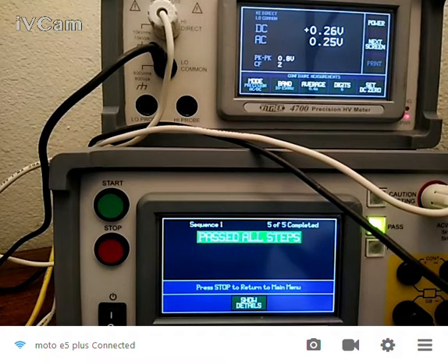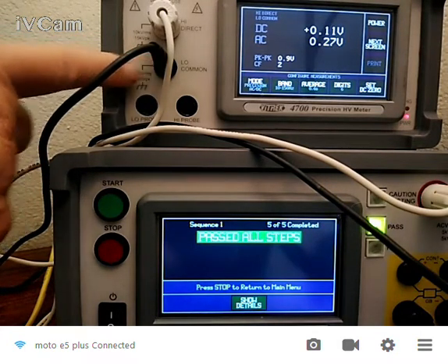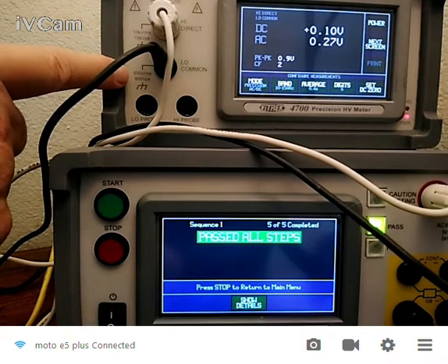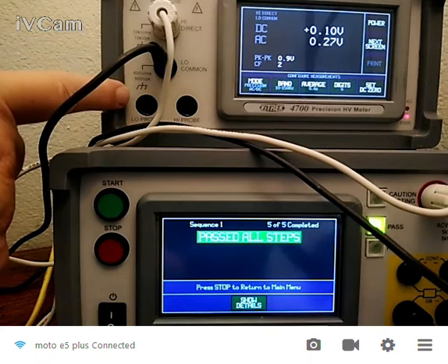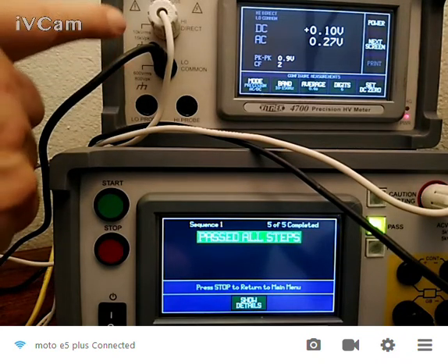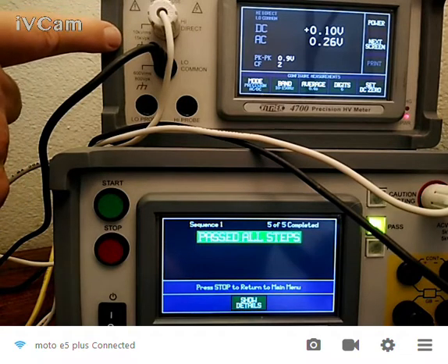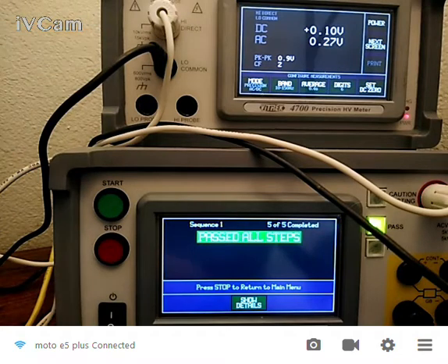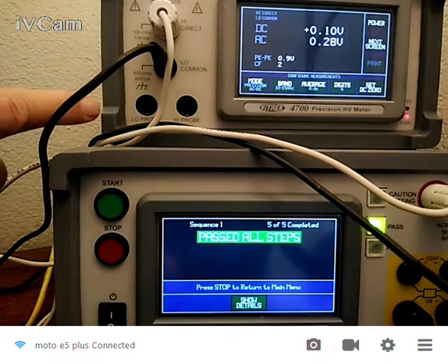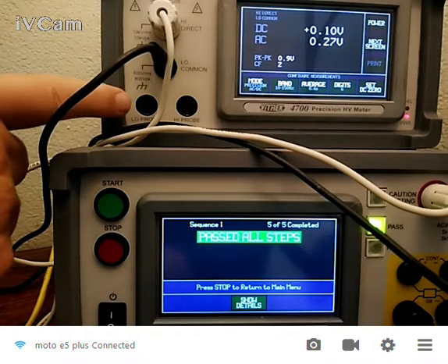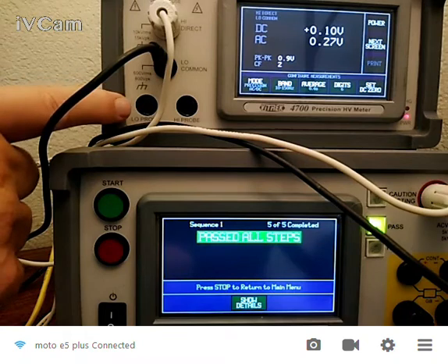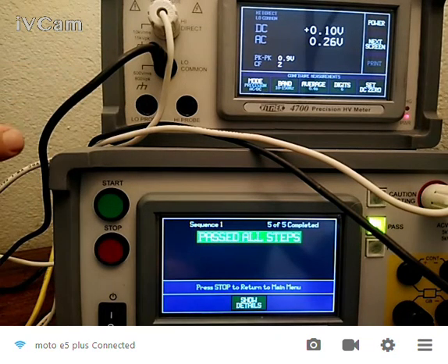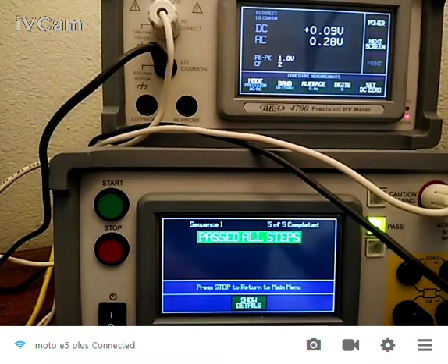You can also have probes for it that will go up to 150 kilovolts as well. Notice that when I connect up, this is my low or common. It's actually floating, but we want you to keep it within 600 volts RMS of ground. That's the maximum you can have that float. And you can have the input here up to 10 kilovolts RMS or 15 kilovolts peak. And again, if you use probes, you can have 2 probes for this. Typically, we just use the low probe, and we have probes up to 150 kilovolts. But if you want to use it as a differential device, you can actually put 2 probes in there, and now it can do full differential measurements to quite high voltages as well.